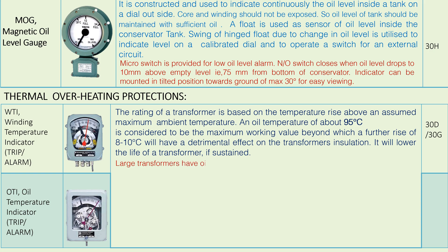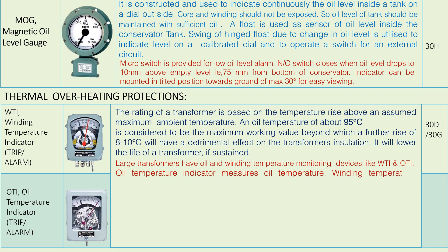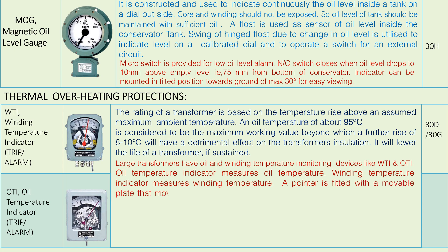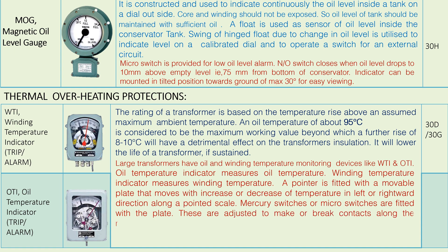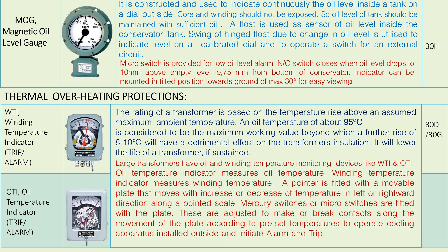Large transformers have oil and winding temperature monitoring devices like OTI and WTI. The oil temperature indicator measures oil temperature. The winding temperature indicator measures winding temperature. A pointer is fitted with a movable plate that moves with increase or decrease of temperature in the left or right hand direction along a pointed scale. Mercury switches or micro switches are fitted with the plate and are adjusted to make or break contacts along the movement of the plate according to preset temperature, to operate cooling apparatus installed outside and to initiate alarm and trip.